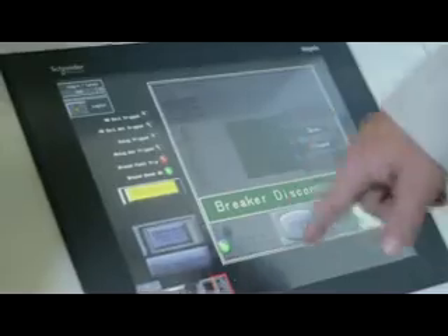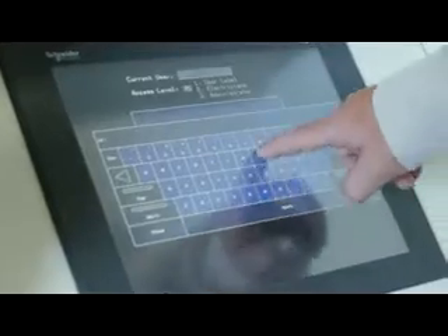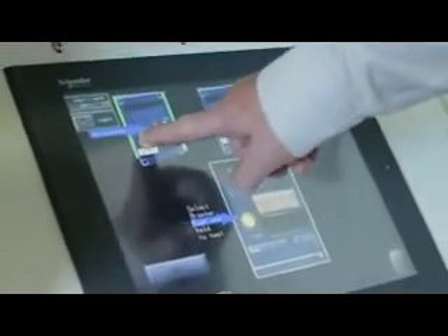Okay. In order to reset that, I can go back into that device as an administrator and change that. So if I was the operator now, I can no longer do anything. If I go to the utilities and I log in as the administrator, and I need to reset that ground fault, I now have the ability to reset that.